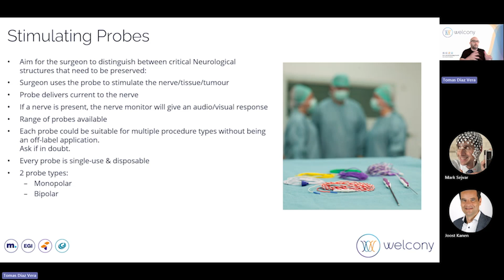Regarding the monopolar probes, we have multiple variants. One of them is the shaft or taper tips, which is important to know that every monopolar probe requires a return needle in order to close the circuit. So the current flow is anode to cathode, and the return needle will close that circuit. Of course, in this case, the monopolars, as you can see in the diagram, once the electrical pulse is delivered, the area is more spread, it's a wide area.